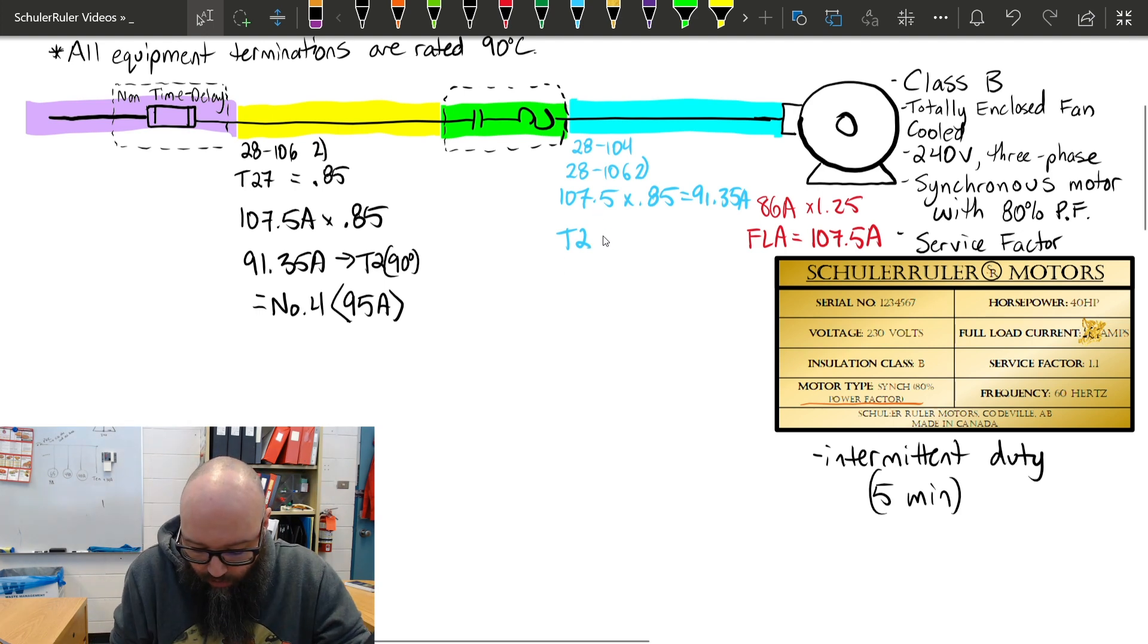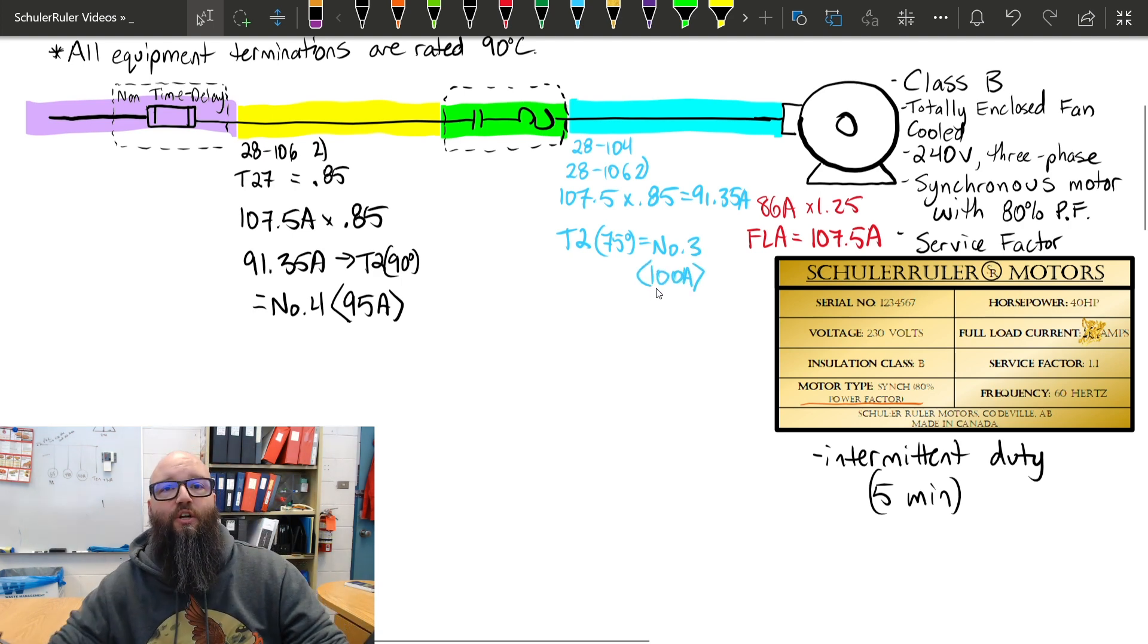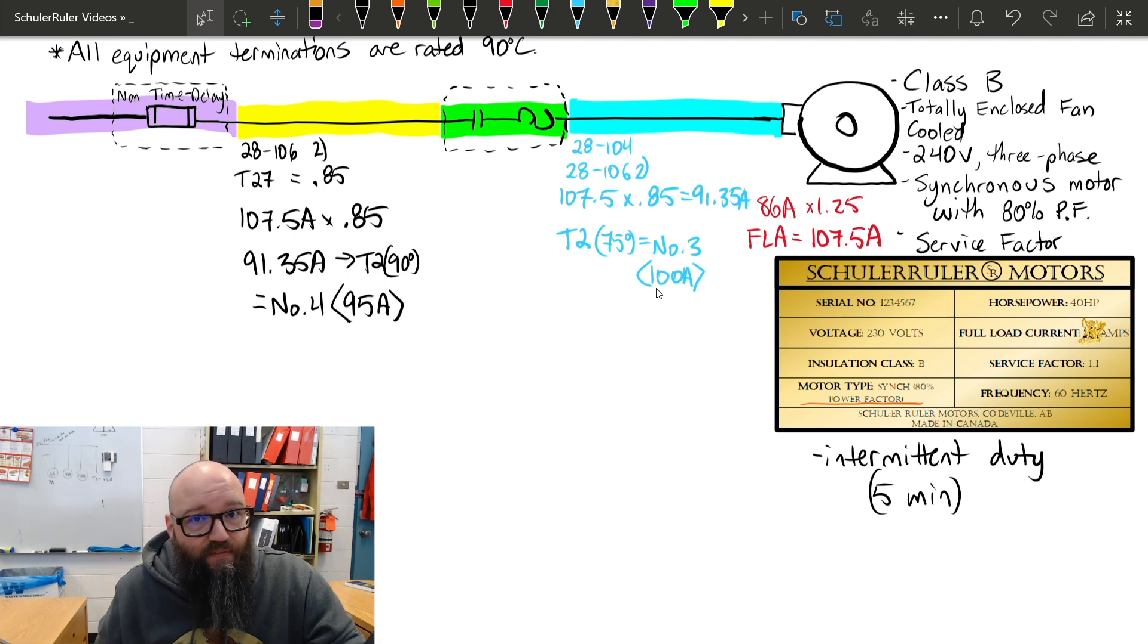We use a 75-degree column for those motor supply conductors, and it actually ends up yielding a number 3. That is good for 100 amps, which makes sense. We see a slightly larger conductor on that motor supply. Think of it acting like a heat sink. That's not specific to synchronous motors. That's just motor supply conductors in general. Always pay attention to that 75-degree note, unless it's a Class A motor and we're using 90-degree insulation temperatures as it notes in 28104 subrule 3.